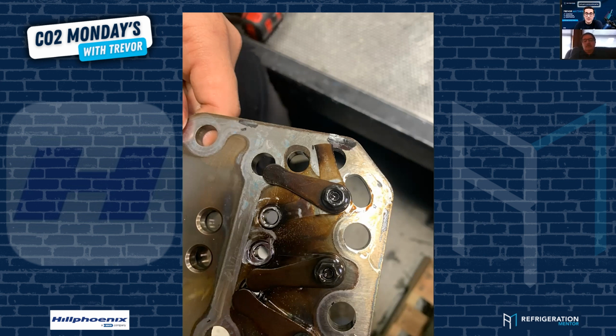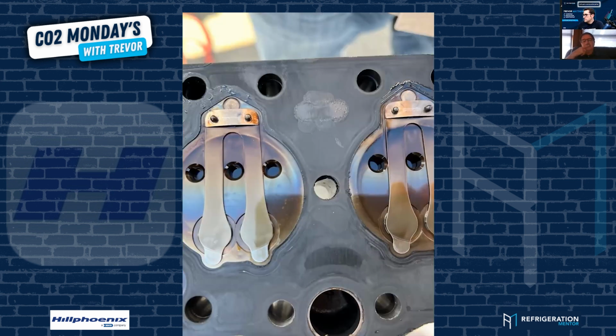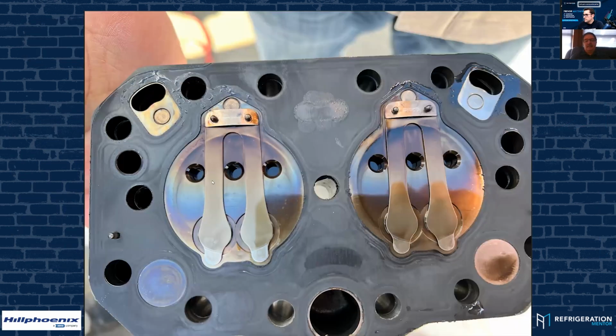Wow. Yeah. So when we put it together the first time and restarted it, I said, well, minimum, you're going to have to put new heads and bolts on here. But then when we started the compressor back up, we got a bird chirp in the bearings. I said, well, now you're going to have to replace that compressor because now the bearings are gone. And yes, once you start heating that oil up, it starts breaking down. Show one of the piston cylinders. Yeah, you can see how that... go back one. That's how hot it got. It changed the color. It actually tempered the valves and changed their rigidity.